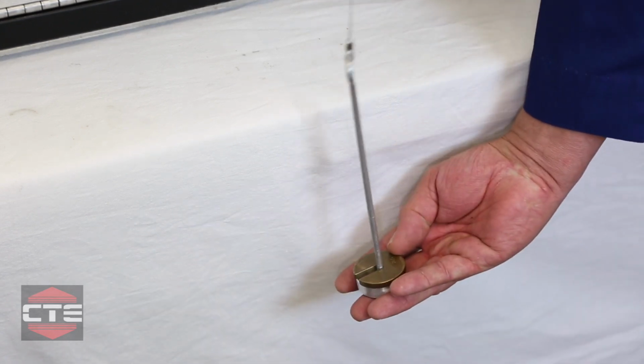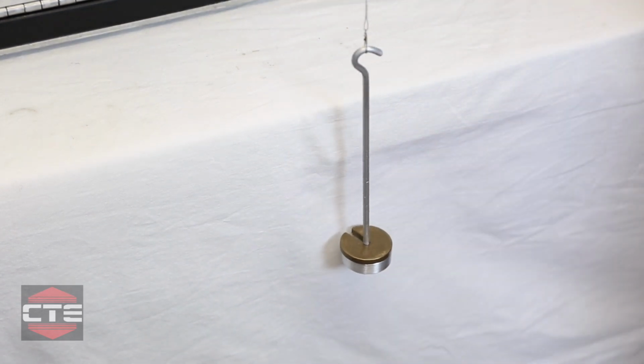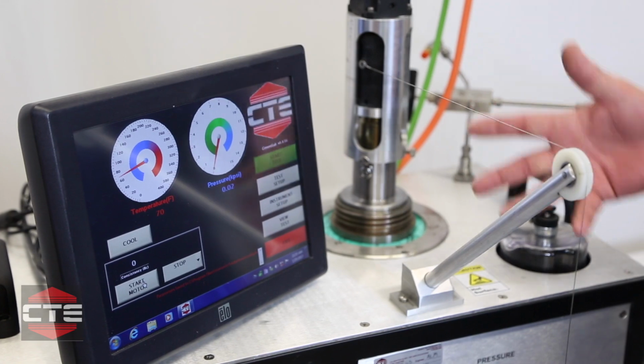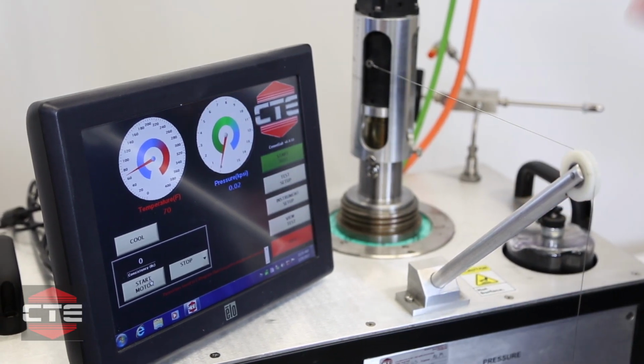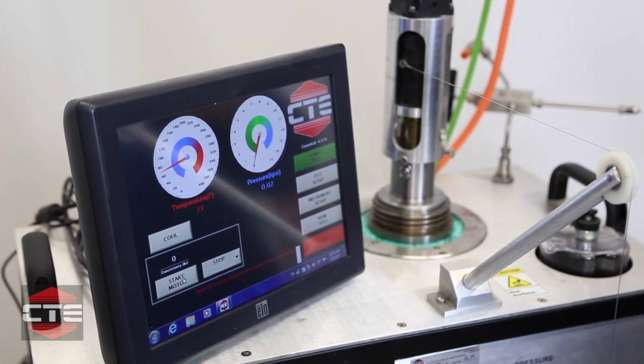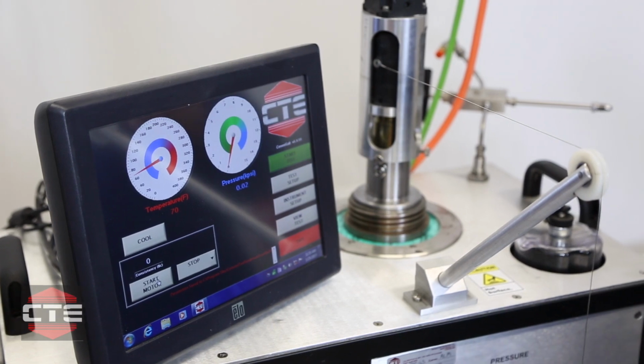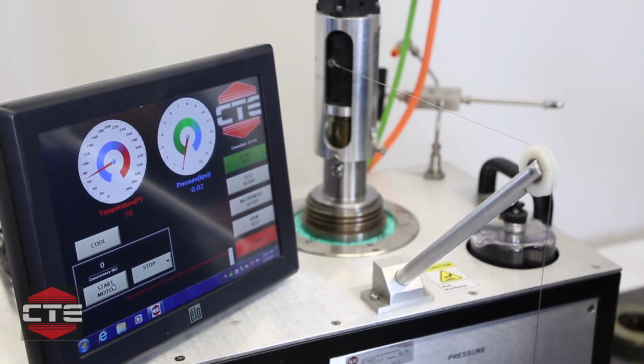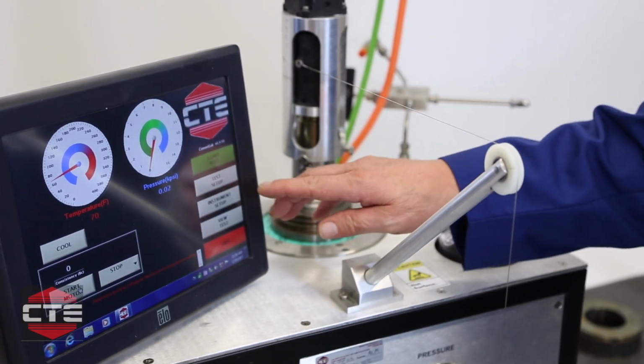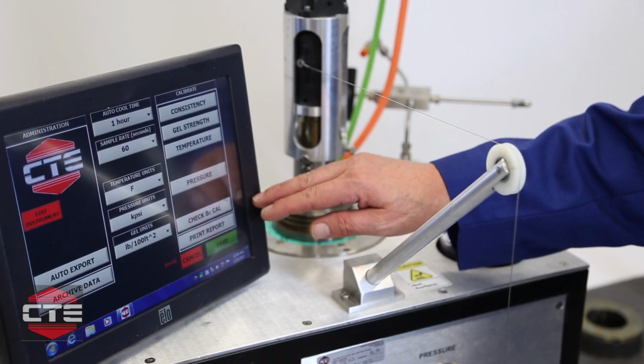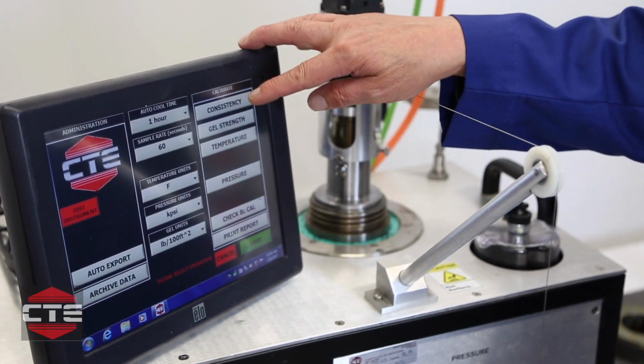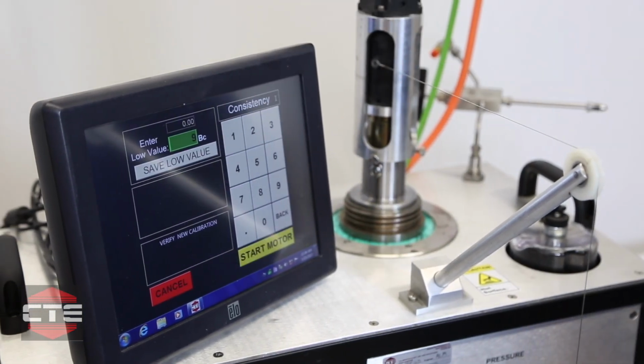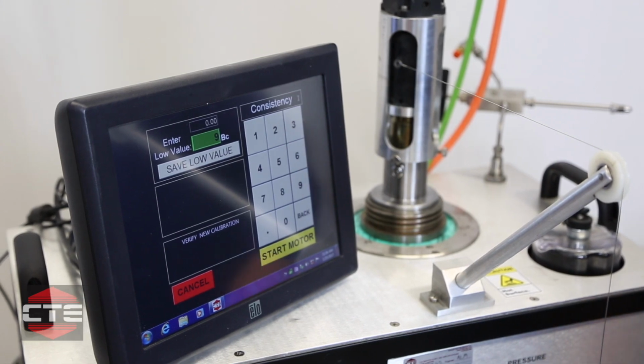If you did not do a gel calibration before you started your consistency, then we recommend before you set up here to energize the motor and let it run for a minimum of 10 minutes, as the calibration works better after the motor is warmed up. Going to instrument setup, we're going to be calibrating consistency, starting with 100 grams, and we have 9 BC already pre-entered into the box. We're going to hit start motor.